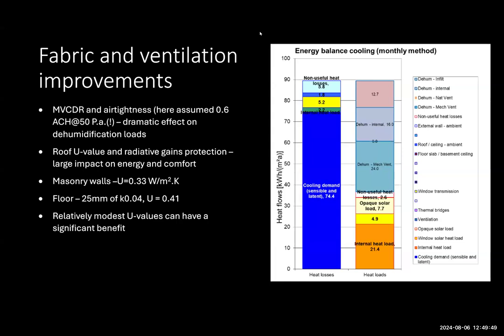So our opaque solar loads we've talked about, and our latent loads are the three at the top. I've split those into infiltration loads - dehumidification necessary because of air leaking into the building - internal loads, which are dehumidification loads from breathing, cooking and so on, and dehumidification loads from mechanical or intentional ventilation, which is the necessary air for good air quality.